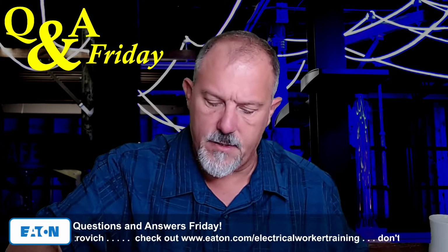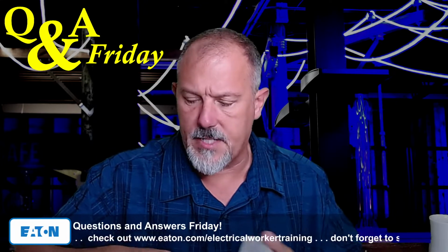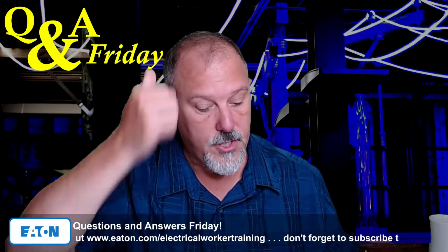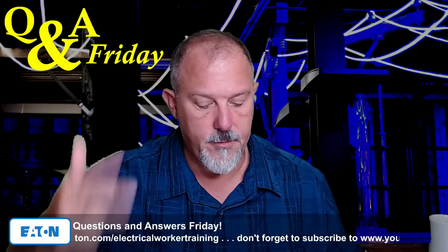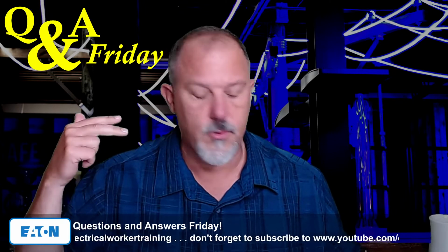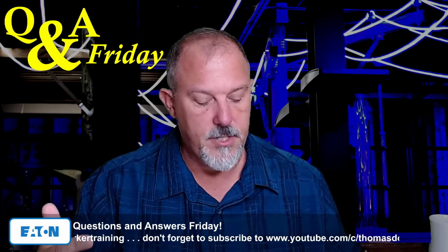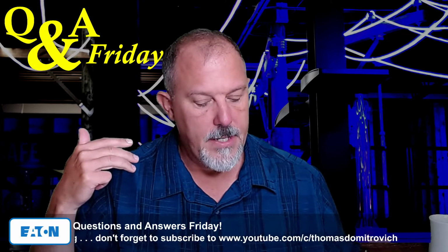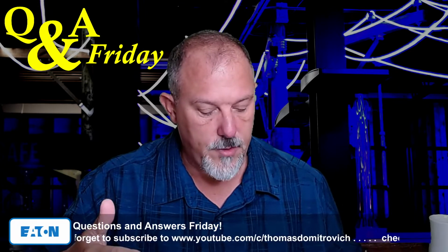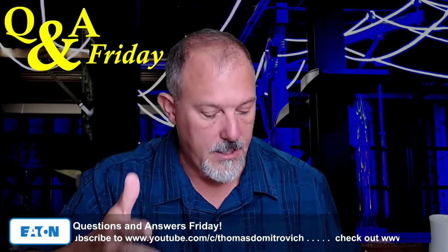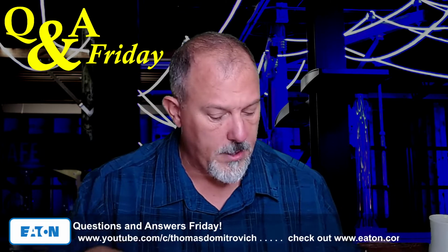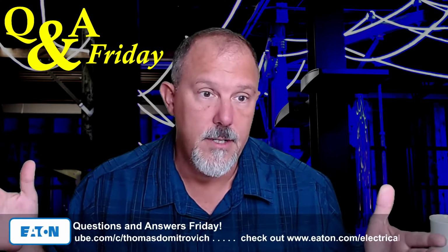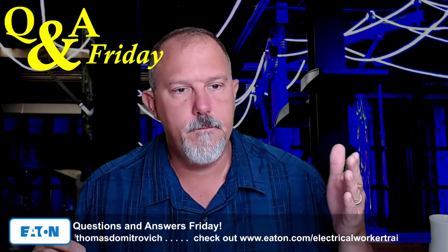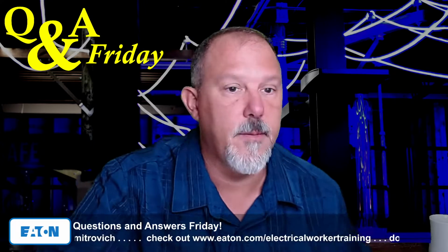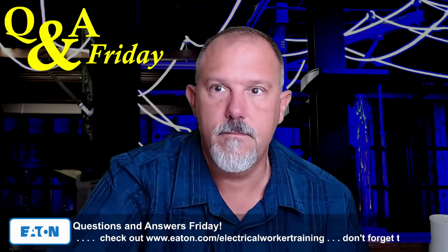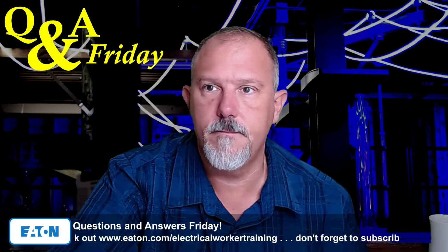240.87, if you have a circuit breaker, 1200 amps and above, you can do zone selective interlocking, differential relaying, an energy reduction maintenance switch with a local status indicator, or an energy-reducing active arc flash mitigation system. You can leverage instantaneous trip. You can leverage the instantaneous override in a circuit breaker, or you can have any other method that you want to do. So I'm not sure what you're talking about there, but maybe I'll learn more as I read on.